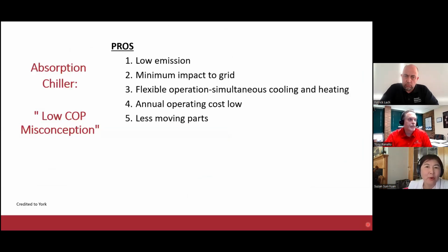It is important to note that COP between centrifugal and absorption chillers is calculated differently. AHRI indicates working conditions to measure COP. Centrifugal chillers are measured with the cooling effect over the compressor work input. For absorption chillers, COP is calculated by the cooling output over the heating source input. The COP for an absorption chiller is low under this measuring metric.